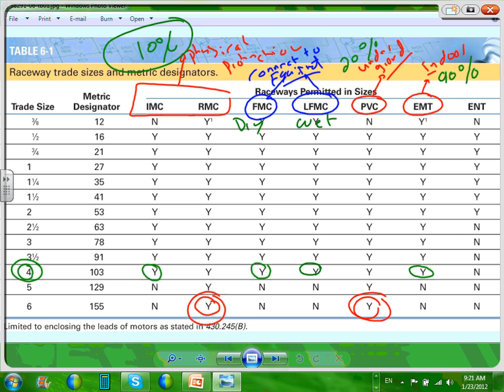PVC or rigid? Can you guys see, a lot of people ignore this when they become designers, and we design 4,000 amp switchgears, and a lot of us use 5-inch and 6-inch conduits all the time. So what's your only option? PVC, and by the way, PVC schedule 80 or rigid are the ones that go all the way up to 6. Any question, guys? So everybody can see the limitation of these conduits, but up to 4, by the way, 4 is nothing to sneeze at. 4 can get you a lot of power.